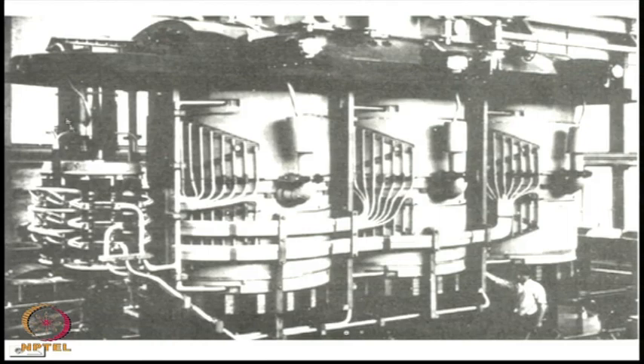Therefore, there will be a section of the winding, usually on the high voltage side, which will have several terminals coming out from them. In this picture, these terminals are shown on the 3 phases, and there will be a selection switch which can choose the terminal at which the transformer external connection is connected at any point. There are two different ways this tap changing can be done. One is called offload tap changing, where during changing from one tap to another, there will be a momentary disconnection of supply, and onload tap changing, where the supply will not be disturbed.